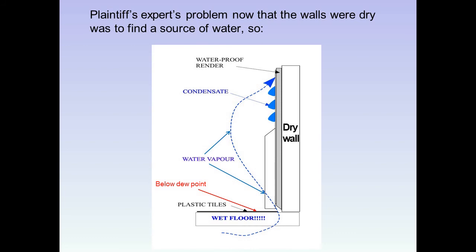The plaintiff's expert had to find a source of water. He proposed that water was coming from the floor-wall junction. We know the wall was dry — it was monitored and evaluated. So he was now claiming the floor was wet. However, the floor was set under plastic tiles and was also below the dew point. He was saying water was evaporating from a position where it should in fact be condensing, and escaping through a very narrow gap then condensing further up the wall. This is total nonsense.